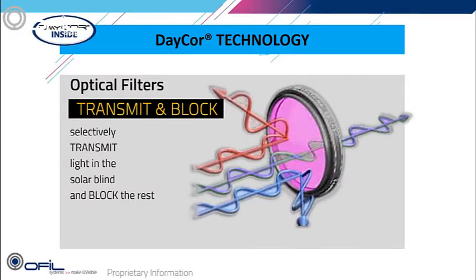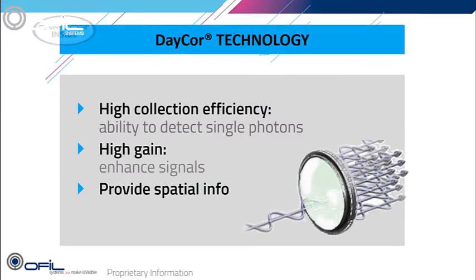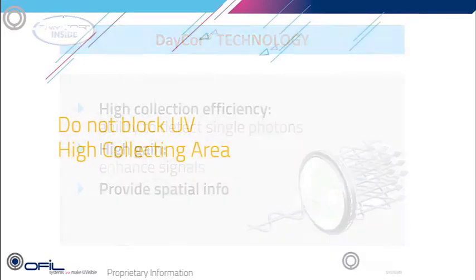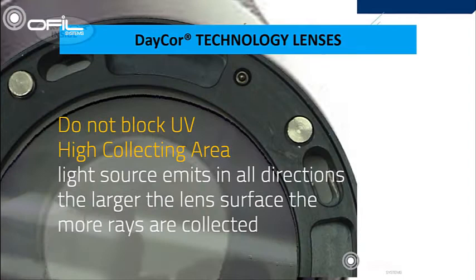The core proprietary optical filters select light in the 240 to 280 nanometer range and transmit it to the detector while blocking the rest. Filter efficiency is measured by the ability to collect as many photons as possible — the more radiation collected, the more information provided about existing discharges. DayCor uses lenses that do not block UV as regular lenses do; DayCor lenses have high UV efficiency and a large collecting area, giving a distinctively high ratio between transmitted UV and blocked visible light.